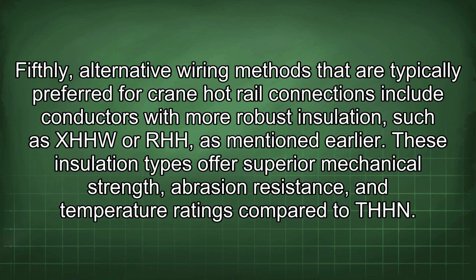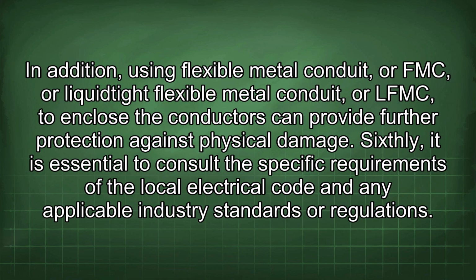Fifthly, alternative wiring methods that are typically preferred for crane hot rail connections include conductors with more robust insulation such as XHHW or RHH, as mentioned earlier. These insulation types offer superior mechanical strength, abrasion resistance, and temperature ratings compared to THHN. In addition, using flexible metal conduit, or FMC, or liquid-tight flexible metal conduit, or LFMC, to enclose the conductors can provide further protection against physical damage.